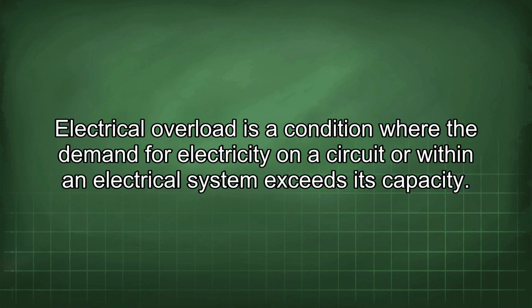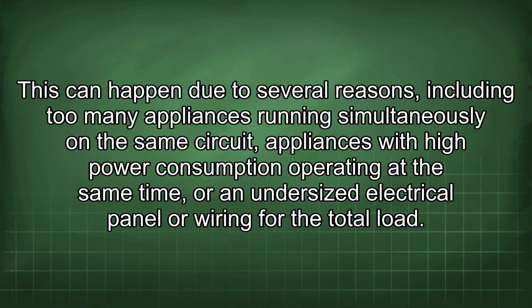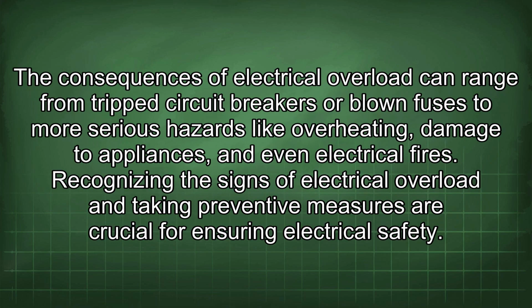Electrical overload is a condition where the demand for electricity on the circuit or within an electrical system exceeds its capacity. This can happen due to several reasons, including too many appliances running simultaneously on the same circuit, appliances with high power consumption operating at the same time, or an undersized electrical panel or wiring for the total load. The consequences of electrical overload can range from tripped circuit breakers or blown fuses to more serious hazards like overheating, damage to appliances, and even electrical fires.